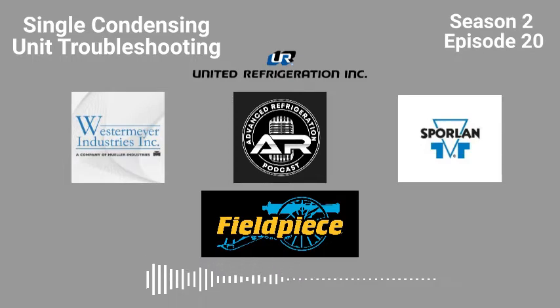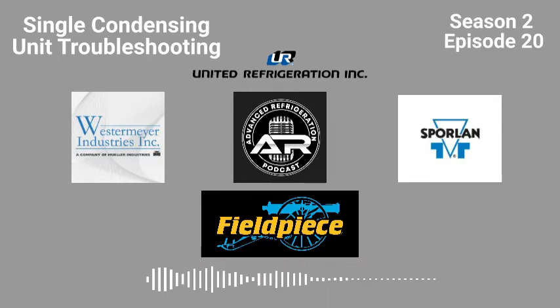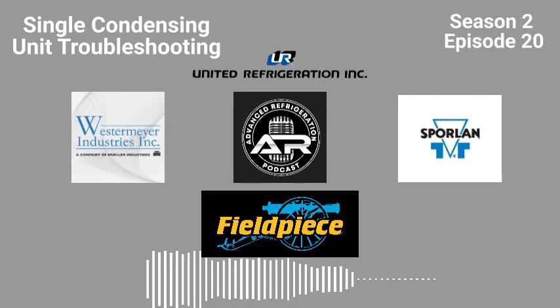So I have a problem, and Kevin and I have talked about this before, with some of the projects at some of the grocery stores where they're putting in three or four open air cases down the store, and they have a single condensing unit. I've seen so many posts on this particular project where they say that there's not a problem, but everything I come up with says that it's oversized. I had two other engineers look into this, just to make sure that I wasn't just full of crap.